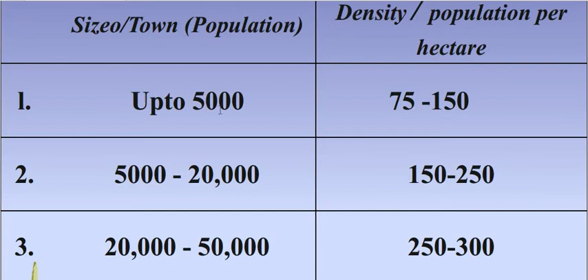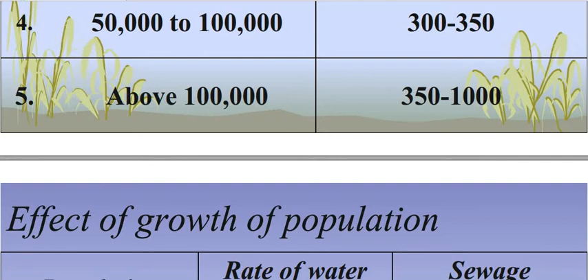population. There are two columns here: the size of the town, given by population, and the density, population per hectare. For a population up to 5,000, the density is 75 to 150. For 5,000 to 20,000, it is 150 to 250. For 20,000 to 50,000, it is 250 to 300. Similarly, for a town of about 50,000 to 1 lakh, it is 300 to 350, and above 1 lakh, 350 to 1000. These are the densities given by the Manual of Sewage Treatment by the Central Public Health Organization.